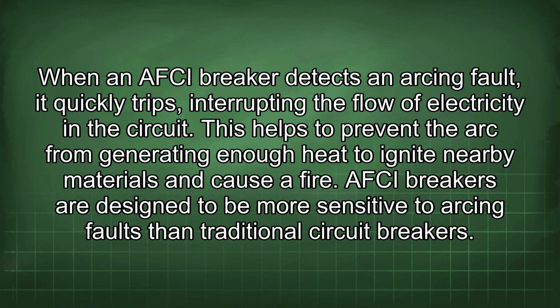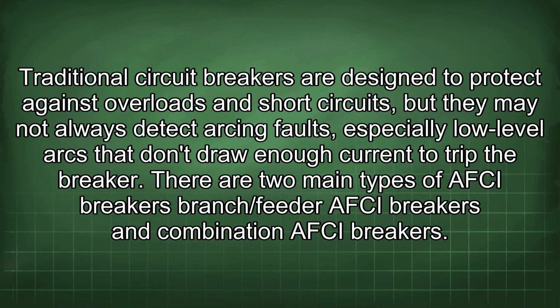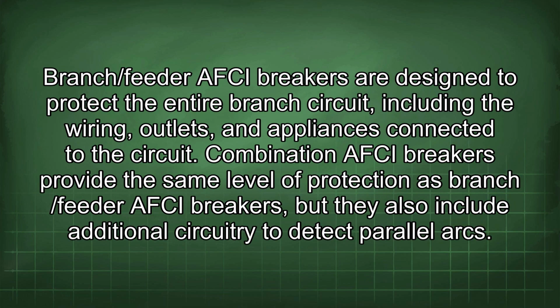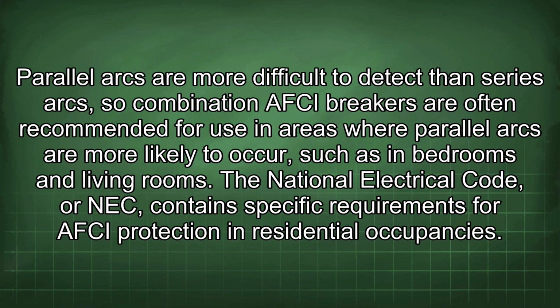AFCI breakers are designed to be more sensitive to arcing faults than traditional circuit breakers. Traditional circuit breakers are designed to protect against overloads and short circuits, but they may not always detect arcing faults, especially low-level arcs that don't draw enough current to trip the breaker. There are two main types of AFCI breakers: branch/feeder AFCI breakers and combination AFCI breakers. Branch/feeder AFCI breakers are designed to protect the entire branch circuit, including the wiring, outlets, and appliances connected to the circuit. Combination AFCI breakers provide the same level of protection as branch/feeder AFCI breakers, but they also include additional circuitry to detect parallel arcs. Parallel arcs are more difficult to detect than series arcs, so combination AFCI breakers are often recommended for use in areas where parallel arcs are more likely to occur, such as in bedrooms and living rooms.